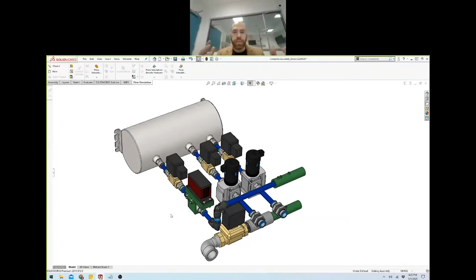Second, now if we start discussing a bit regarding how it works, let's say the machine will be linked to the wall. In the wall, there are two outlets, which are the medical air and the medical oxygen. The machine will take the medical air, go through a pressure regulator. The same goes for medical oxygen as well. Then they go through valves into a mixing chamber. This is where we do the mixing to make sure that the amount of oxygen required by the physician or by the healthcare provider is the amount that we actually deliver. After the mixing chamber, it goes to a variable flow valve, and this is something that we designed from scratch.